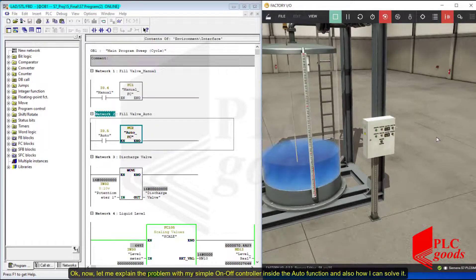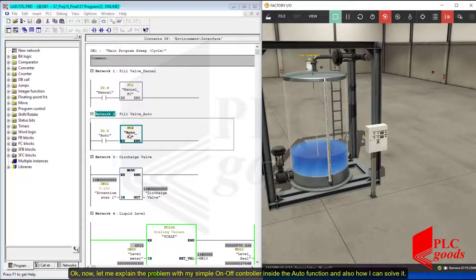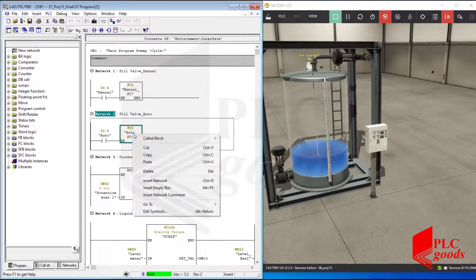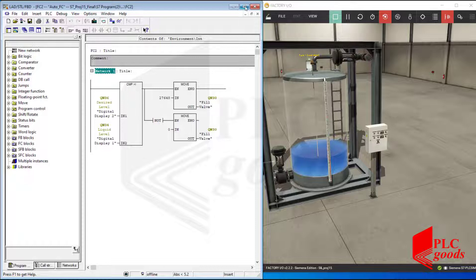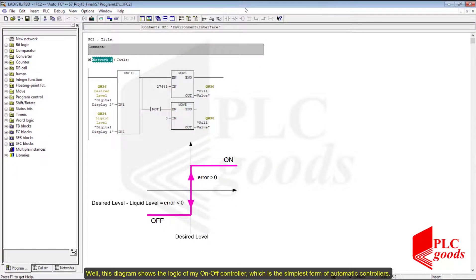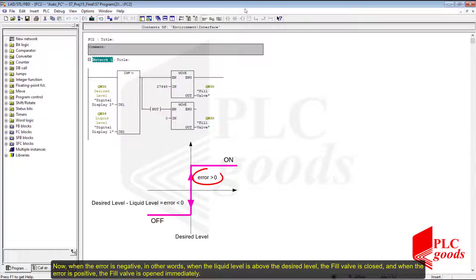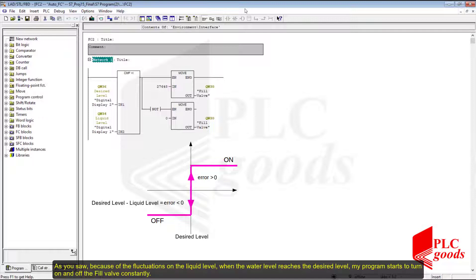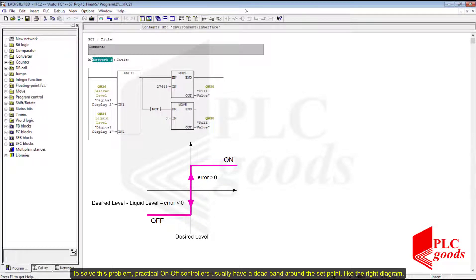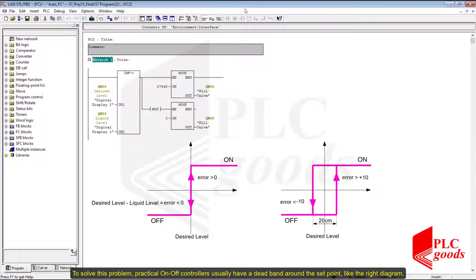Now let me explain the problem with my simple on-off controller inside the auto function and also how I can solve it. This diagram shows the logic of my on-off controller, which is the simplest form of automatic controllers. When the error is negative — in other words, when the liquid level is above the desired level — the fill valve is closed. When the error is positive, the fill valve opens immediately. Because of fluctuations, when the water level reaches the desired level, my program starts to constantly turn the fill valve on and off. To solve this problem, practical on-off controllers usually have a dead band around the set point.